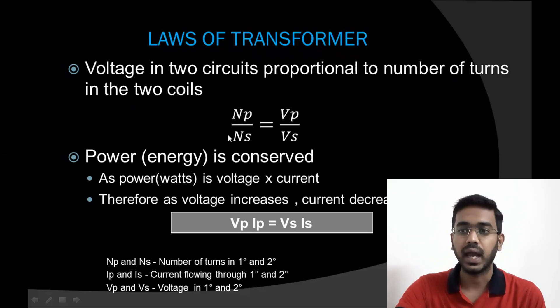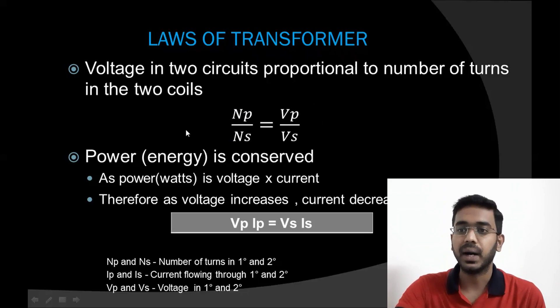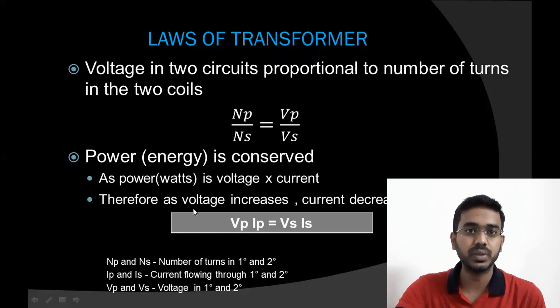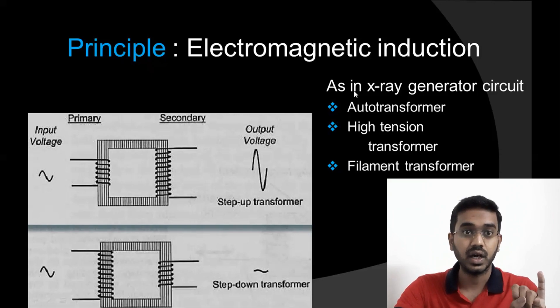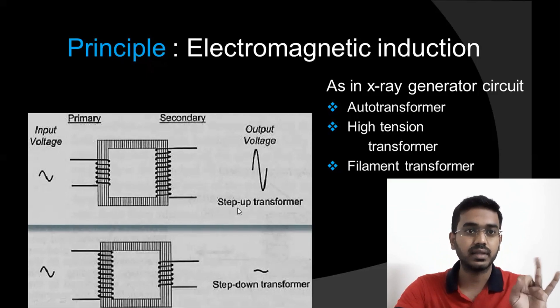The equation for this law is Np/Ns = Vp/Vs. The second law is that power is conserved — power means voltage multiplied by current. If we want voltage to be increased, the current will be decreased proportionally; they are inversely related. The principle of a transformer is electromagnetic induction. The types of transformers used in the X-ray generator circuit are: first, auto transformer; second, high tension transformer, which is a step-up transformer; and third, filament transformer, which is a step-down transformer.